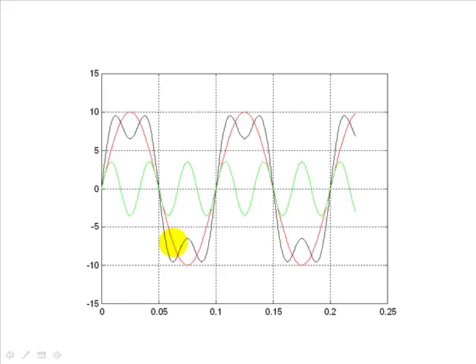we realize that voltage is the sum of two sinusoidal voltages. One voltage of 60 Hz, this one, and one voltage of 180 Hz. That is, now we do not have triple frequency in the magnetization current, but the price we pay is that now we have a triple frequency voltage, which is visible by the client, by the customer, and that is not good and not acceptable.